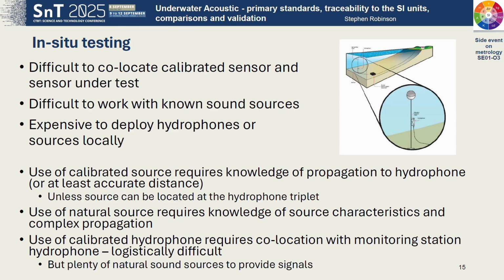And that's much more difficult for hydroacoustics than it is for seismic acoustics and infrasound, because it's difficult to access the measurement stations. Essentially, if they're on land, you can basically co-locate a calibrated reference device and measure simultaneously on the reference device and on the sensor that's used on the station. You can't easily do that for the hydroacoustic stations because they're in the middle of an ocean 1,000 meters down, maybe close to an island, but not readily accessible.